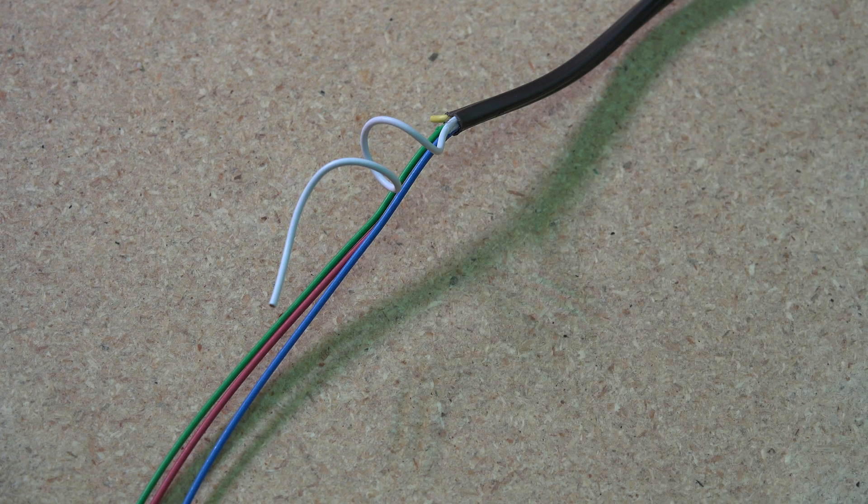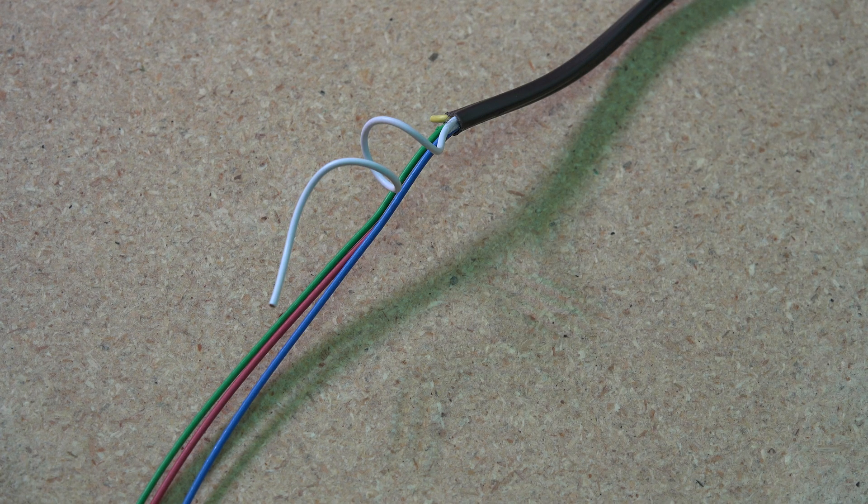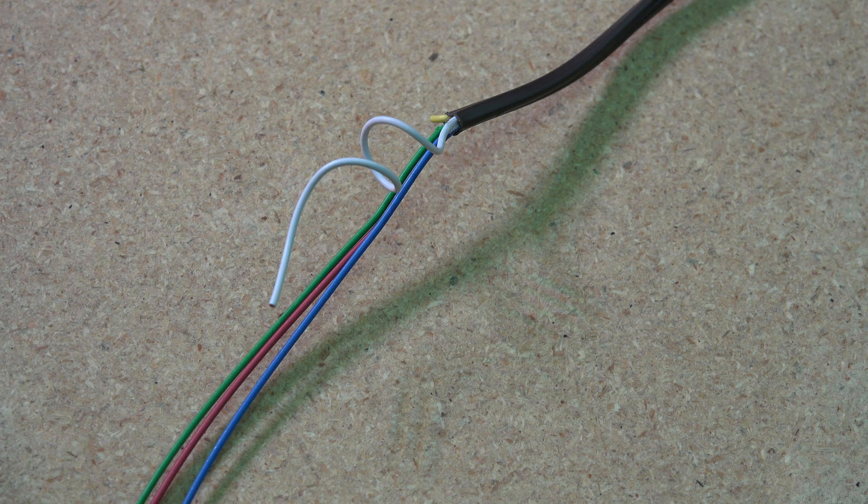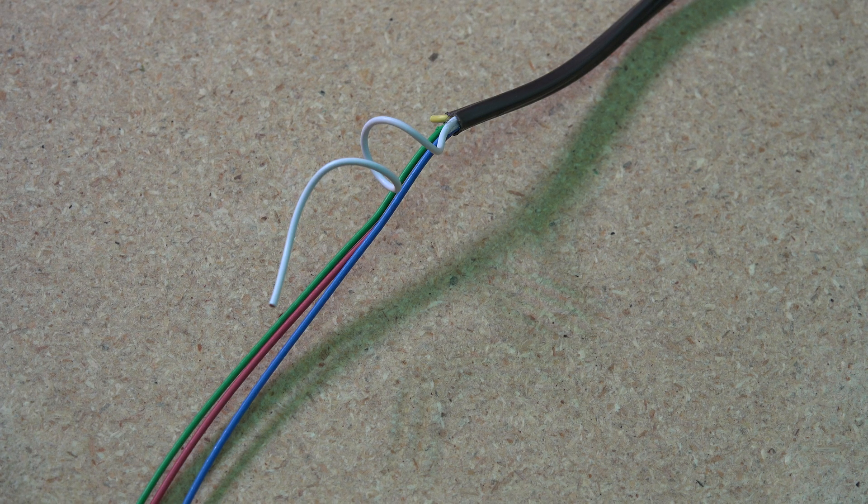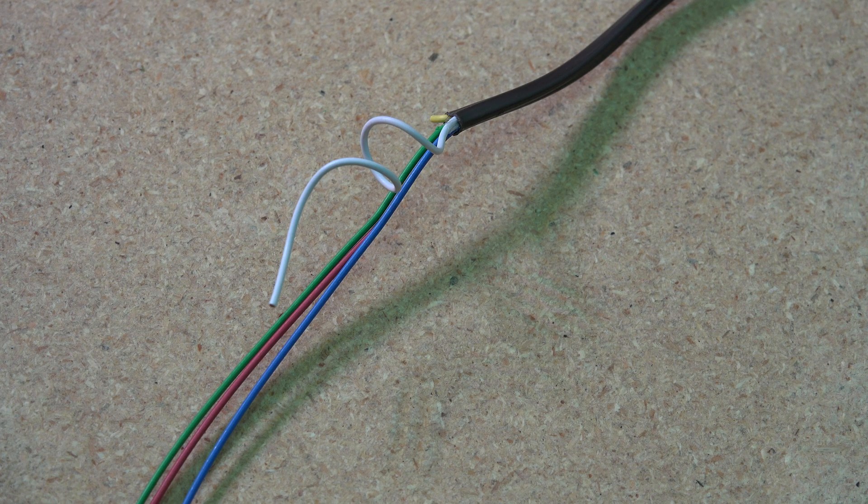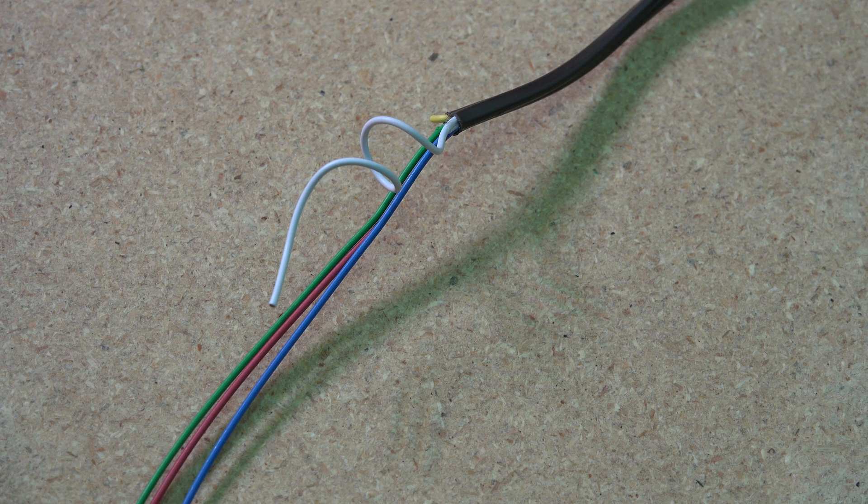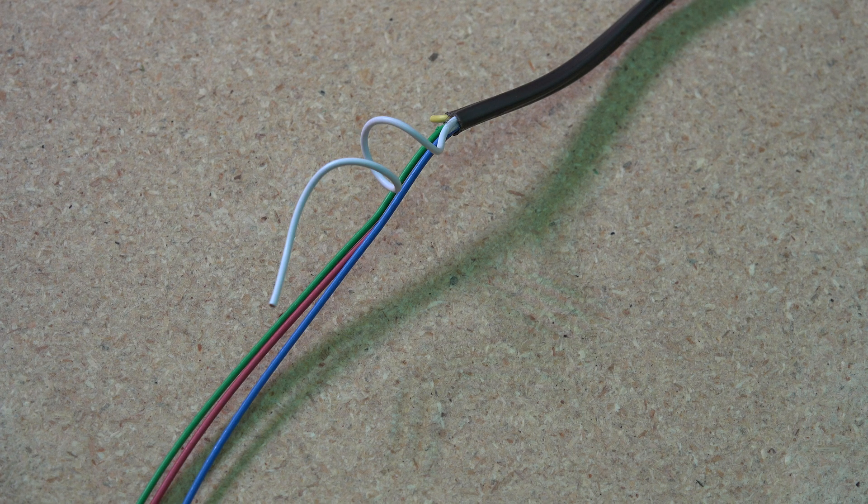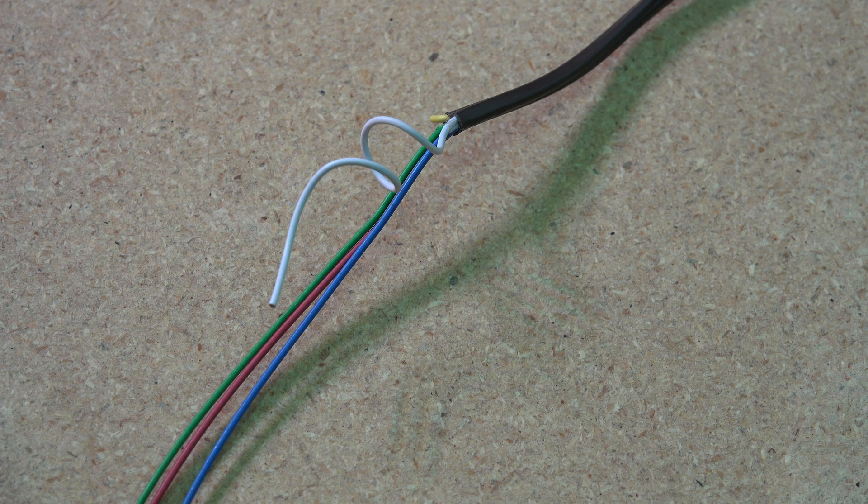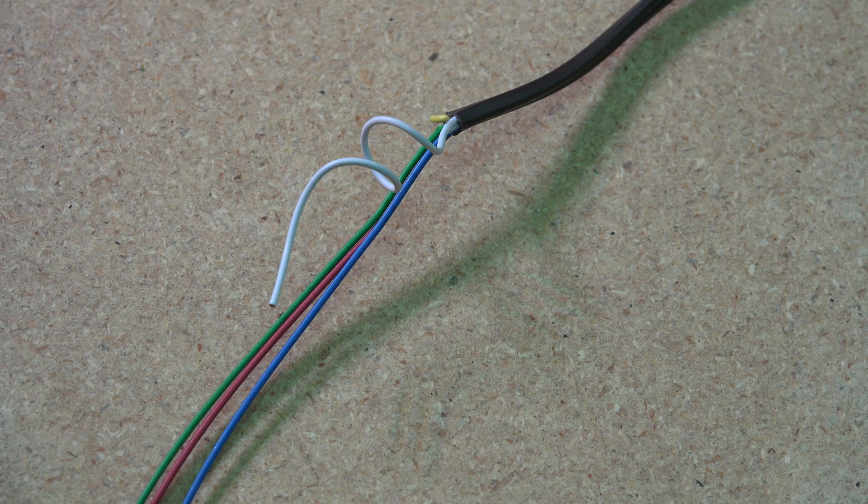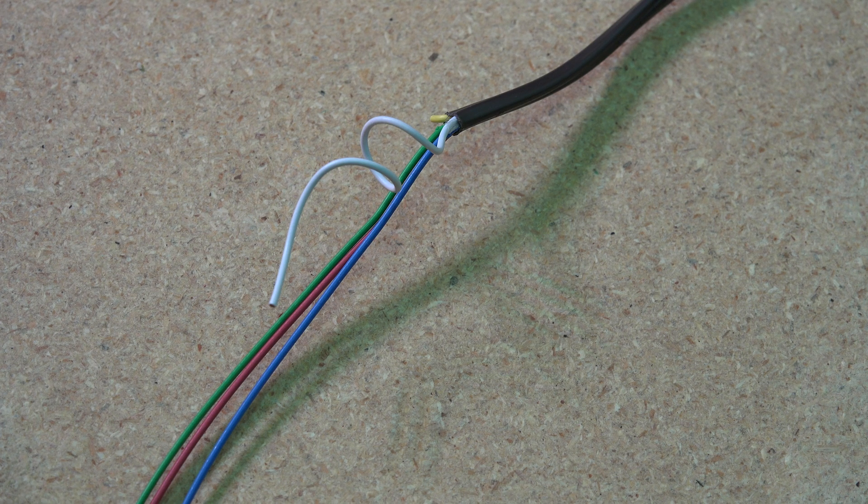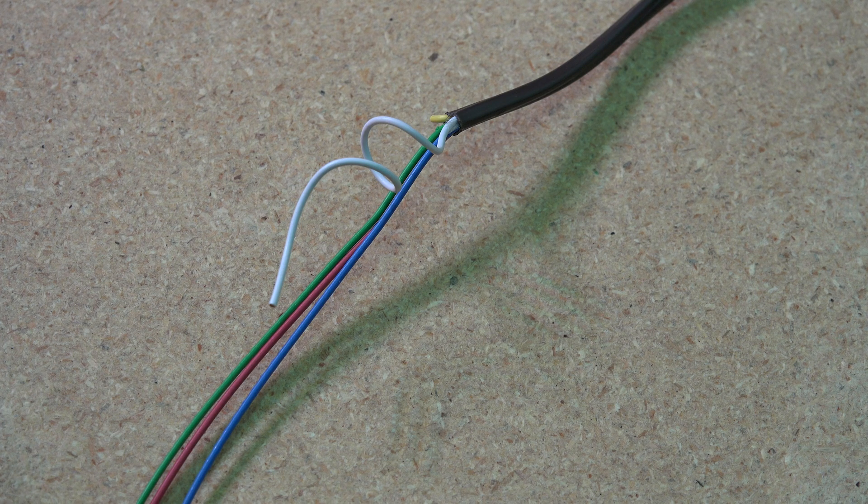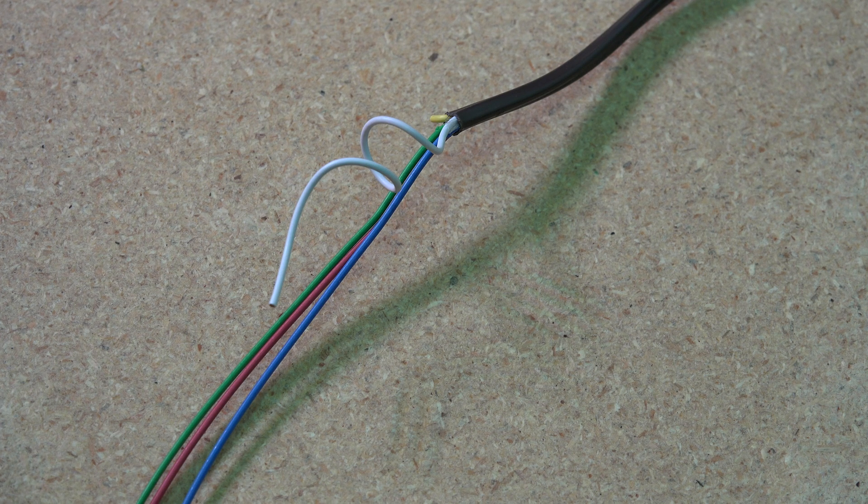Moral of the story is look at the ends of the wires before you decide you have to put a new thermostat wire in the wall, which can be a fairly long job sometimes - not always, but oftentimes it's a fairly long job. And this you could conceivably fix in a very short period of time. Anyway, that's it on this one.